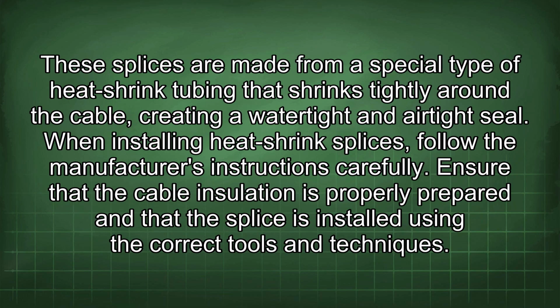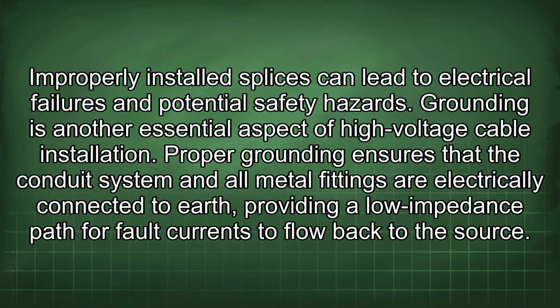These splices are made from a special type of heat-shrink tubing that shrinks tightly around the cable, creating a watertight and airtight seal. When installing heat-shrink splices, follow the manufacturer's instructions carefully. Ensure that the cable insulation is properly prepared and that the splice is installed using the correct tools and techniques. Improperly installed splices can lead to electrical failures and potential safety hazards.